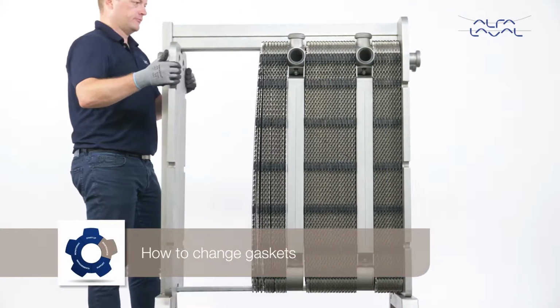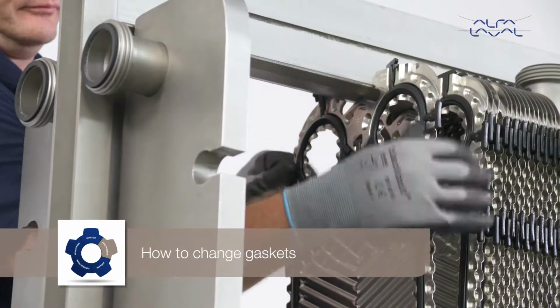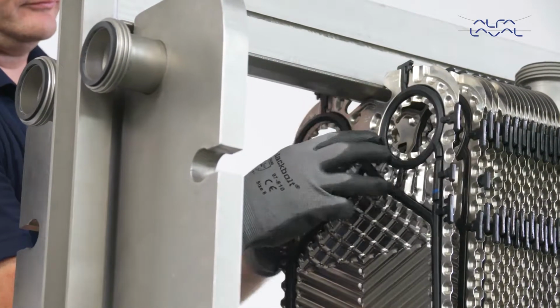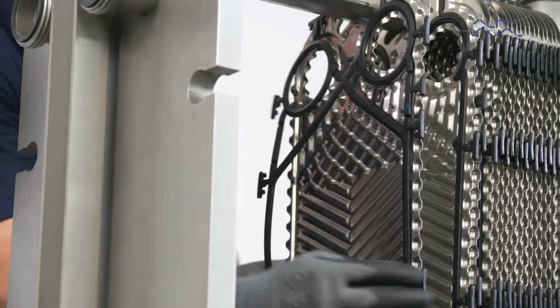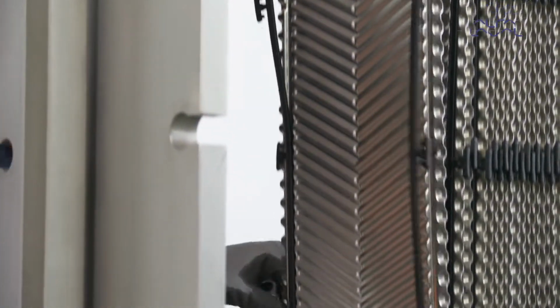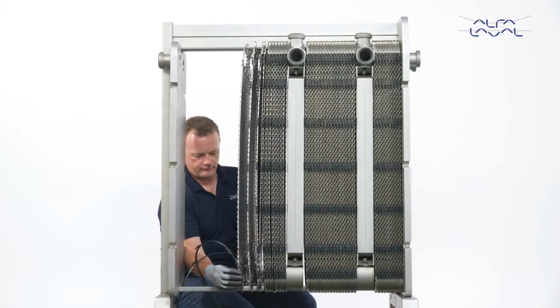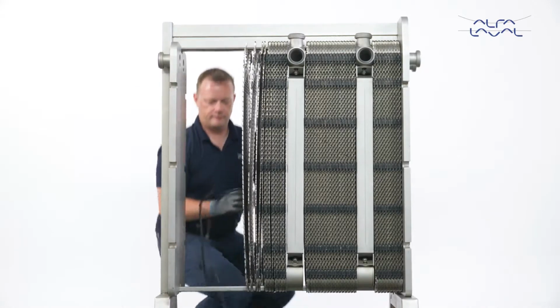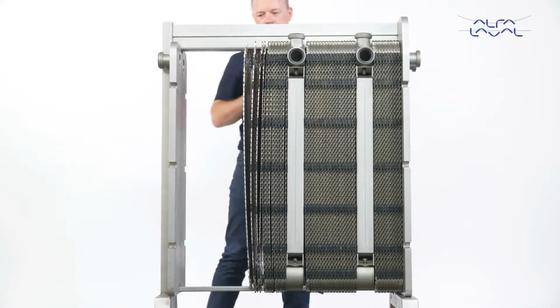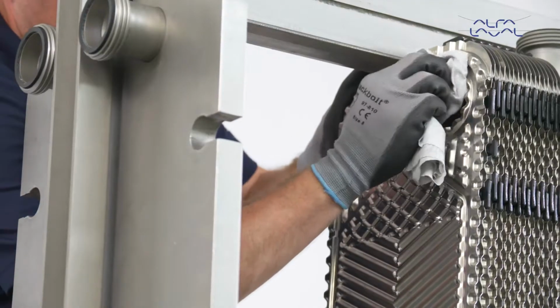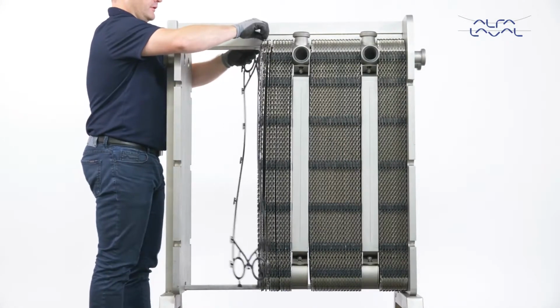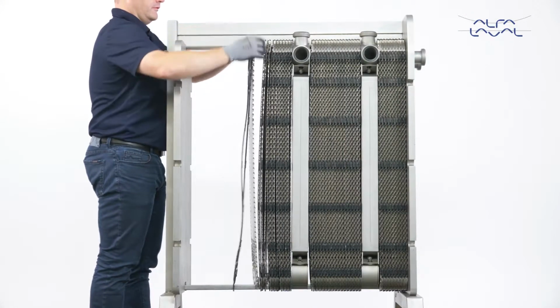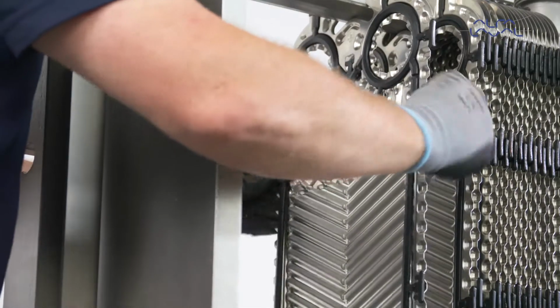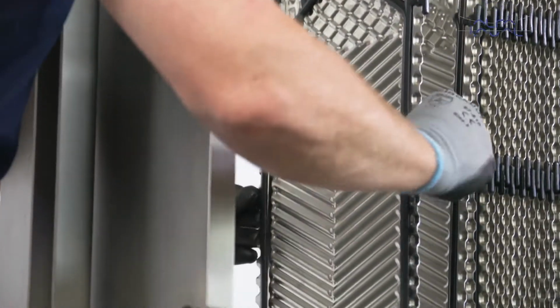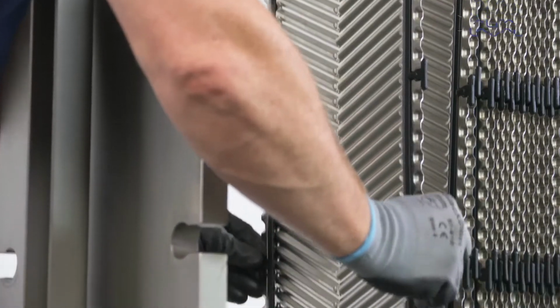How to change gaskets. First, remove the old gaskets. Make sure that all sealing surfaces are dry, clean, and free of foreign matter such as fat or grease. Now attach the Alfa Laval clip-on gasket to the plate. Secure the gasket tabs under the edge of the plate. Repeat the same procedure, changing the gaskets on all plates that require regasketing.